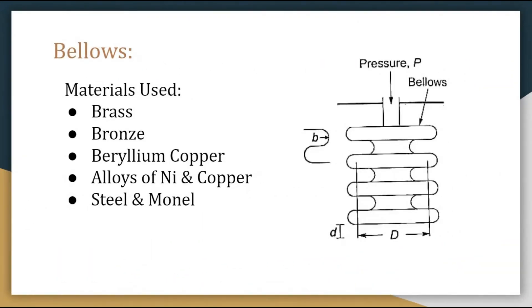The next element is bellows. The materials used for bellows are brass, bronze, beryllium copper, alloys of nickel and copper, steel, and monel, etc. As you can see in this diagram, bellows is basically a series of circular parts resembling the folds in an accordion. These parts are formed or joined such that they are expanded or contracted axially by change in pressure. Change of pressure leads to the expansion and contraction of the bellows element.